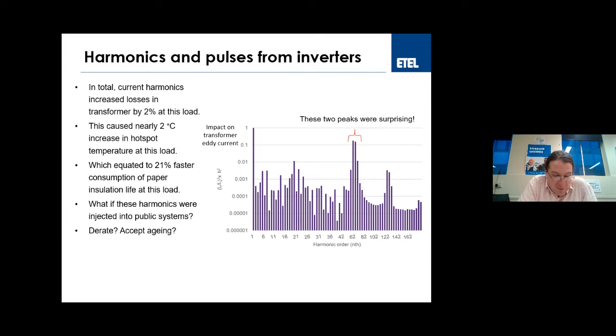Now, I know a lot of people use total harmonic distortion. According to the IEC, that only takes into account harmonics up to the 40th order. So there's no regulation in that IEC standard on harmonics higher than the 40th. What we're seeing here is that some of our inverter companies are now increasing the switching frequency of their inverters, and it's pushing these harmonics up into a higher order.